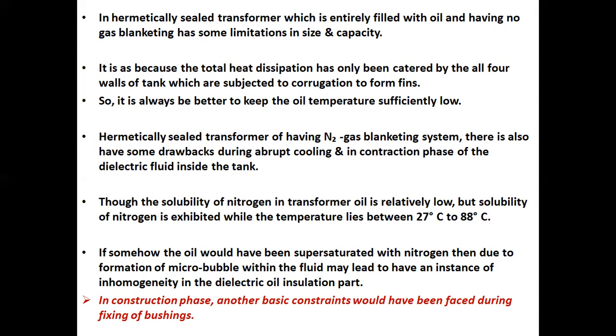Most important, though the solubility of nitrogen in transformer oil is relatively low, solubility of nitrogen is exhibited while the temperature lies between 27 degrees centigrade to 88 degrees centigrade. If somehow the oil becomes supersaturated with nitrogen, then the formation of microbubbles within the fluid may lead to an instance of inhomogeneity in the dielectric oil insulation part.